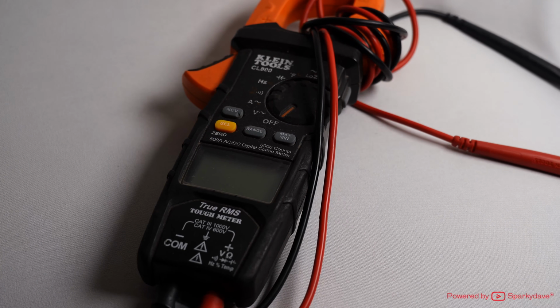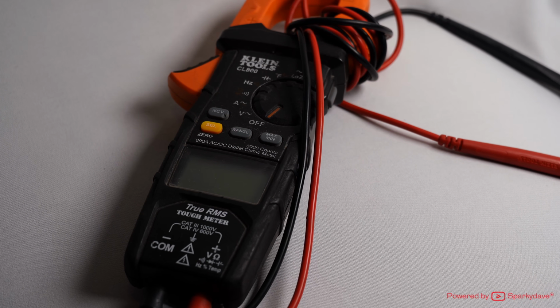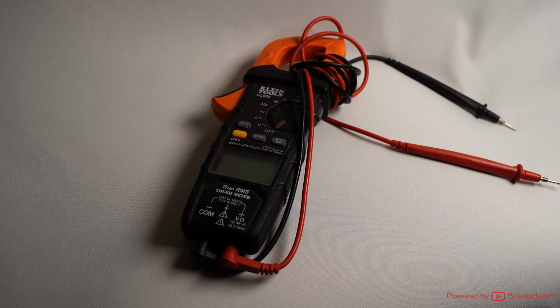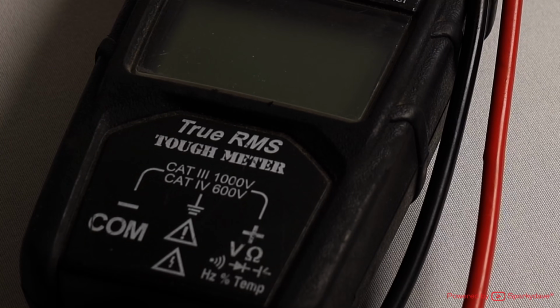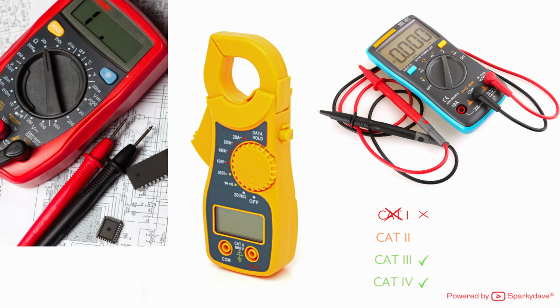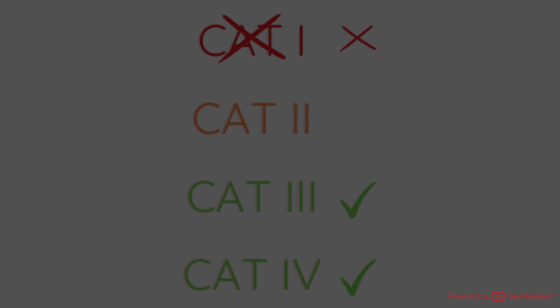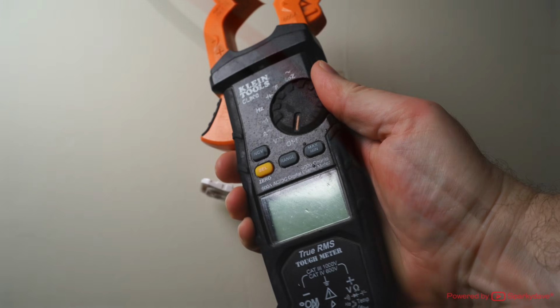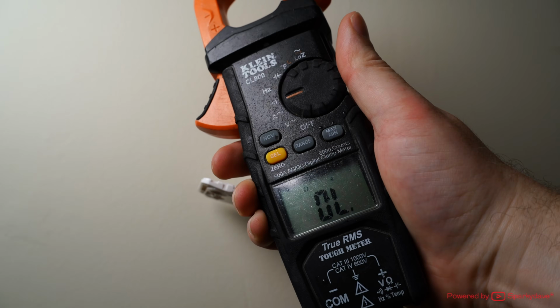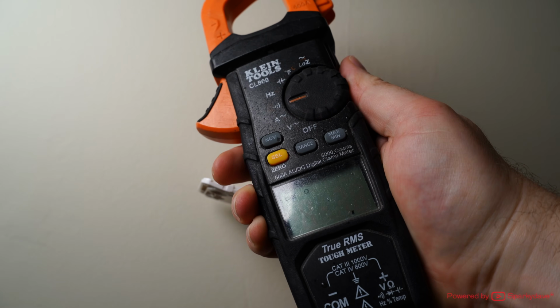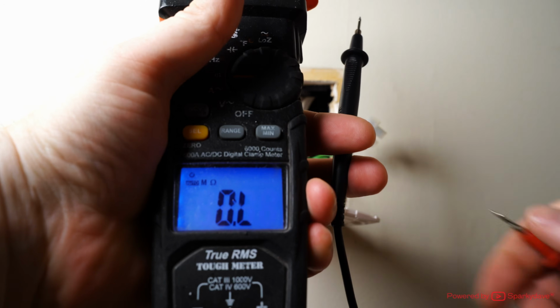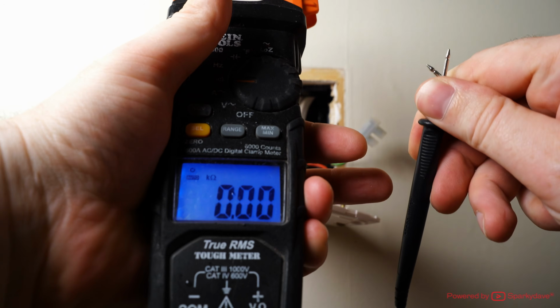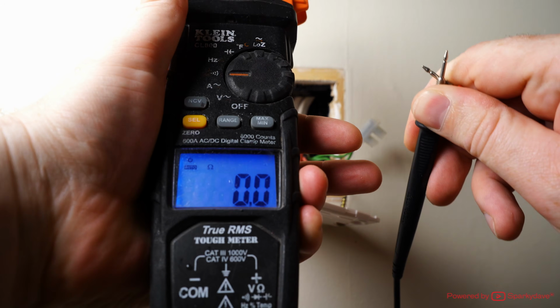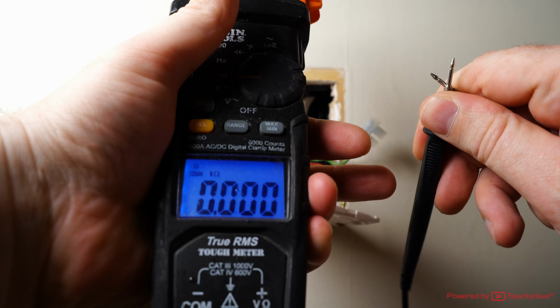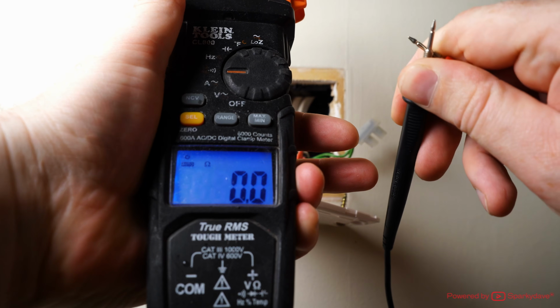To verify the voltage behind the light switch, use an appropriately rated multimeter. Check the category rating on the multimeter before proceeding. The first part of testing is to ensure the multimeter leads are not damaged. For this, switch the multimeter to resistance, ohms, and check the resistance between the leads is less than 0.5 ohms. Here the resistance between leads is 0.0 ohms, which is perfect.